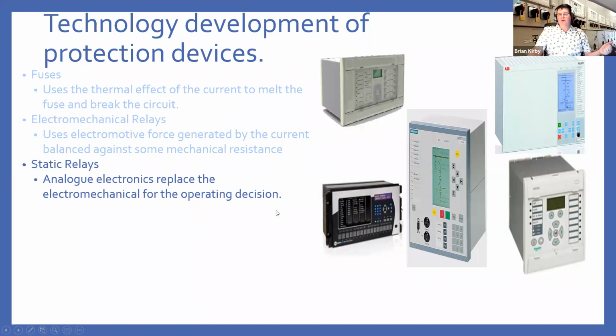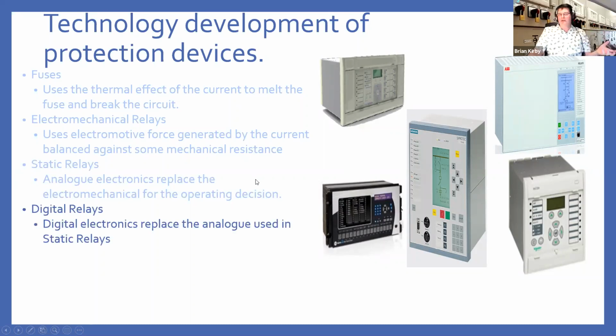Static relays came along around about the 1960s, and they replaced the electromechanical devices with analog electronics. So it's still doing the same comparison, but instead of using a physical movement, it now does a magnitude comparison and then uses that to switch the output decision. Digital relays came along in the 1980s. And again, that's an evolution of technology. So in the 1980s, you would have had the widespread use of the early 4-bit, 8-bit and 16-bit microprocessors, but the functionality was still very limited. You generally didn't have user displays or anything like that. It was all done by some sort of plug, switch and a process to configure. And generally there were still single function devices.